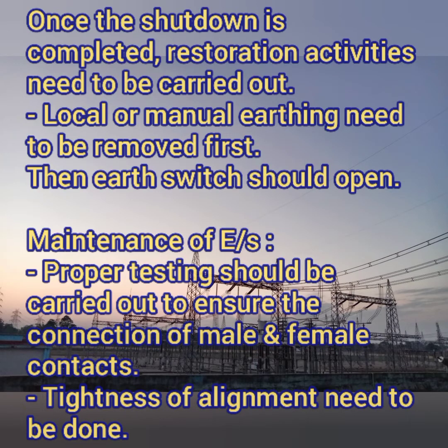Once the shutdown is completed, restoration activity is to be carried out, which means normalizing the area where the shutdown has been taken. For that, we need to ensure that the local or manual earthing needs to be removed first. Because the earth switch operation we can see in the BCU or HMI screens, but the local earthing done manually for our safety purpose — we need to physically ensure that the local earthing has been removed.